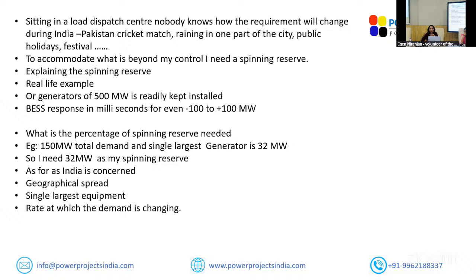Then there is BESS, which responds in milliseconds—minus 100 megawatt to plus 100 megawatt, or as I mentioned, converted to 500 megawatt, because in milliseconds you can ramp up the demand. So what percentage of spinning reserve is needed? If a country's total demand is only 150 megawatt, like a South African country, then it's based on the single largest generator.